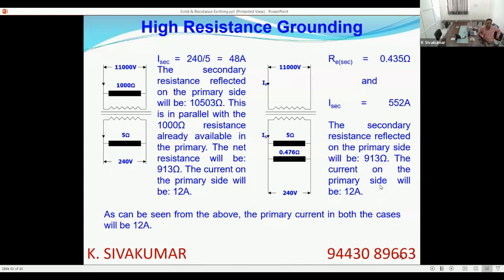My intention is to limit the HT side current to 12 amperes. On the left hand side, I am achieving that by providing a 1000 ohm 11 kV NGR or resistor. On the right hand side, I am achieving my goal by connecting a 240 volt 0.476 ohm resistor. So, which will be economical? We always say that the advantage of NGT lies in going for a very low value resistor insulated to a very low voltage. The cost of the resistor and the size of the resistor box will be very, very negligible compared to connecting a high voltage resistor in the HT neutral directly. This is what I wanted to convey.